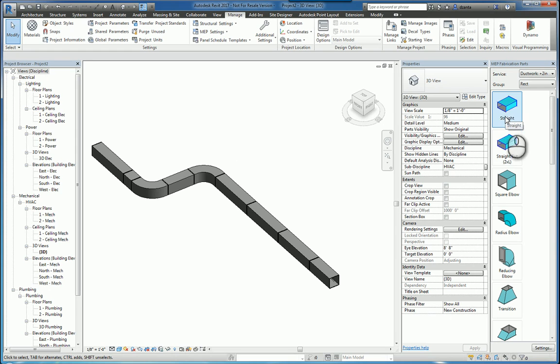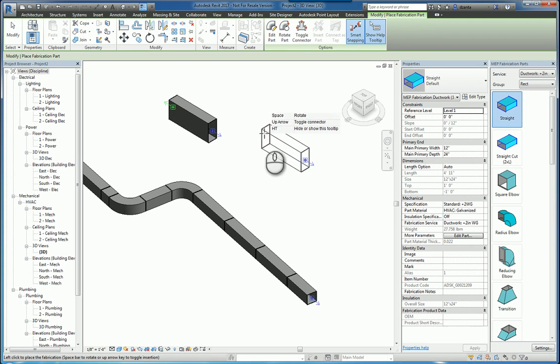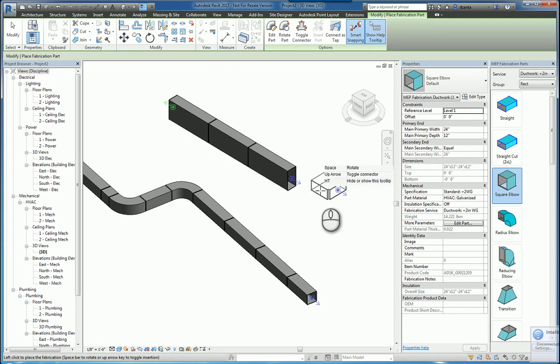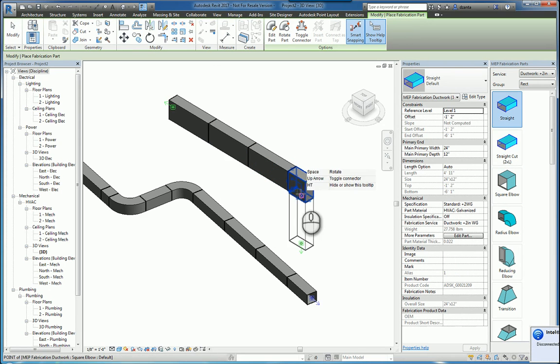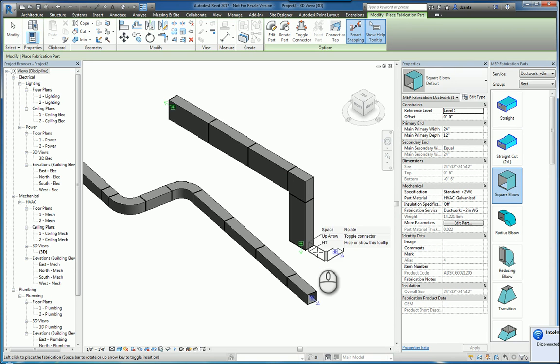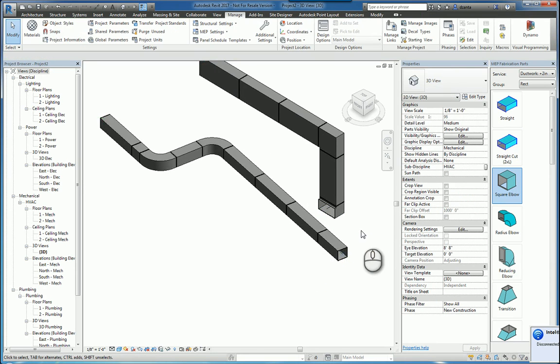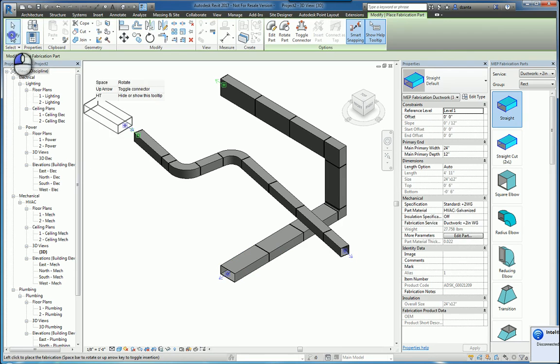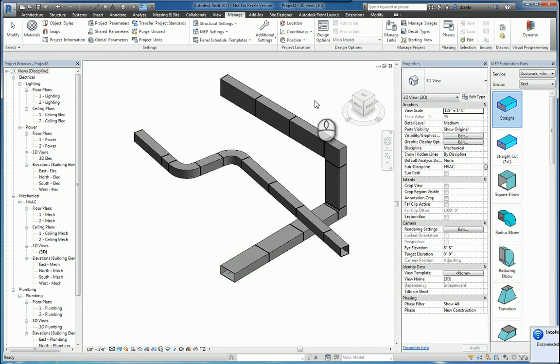Now, if you want to build them from scratch, you can just click over here, pick the service you want, pick the group you want, pick the type of object you want to work with, and then click to start placing them. You'll notice they have connectors on either end and will snap into position. If you need to move one or rotate, you can use the spacebar and click to place. It will automatically orient based on how you've positioned it. These fabrication tools give you preloaded content — you can click and drag and use them to build your system.